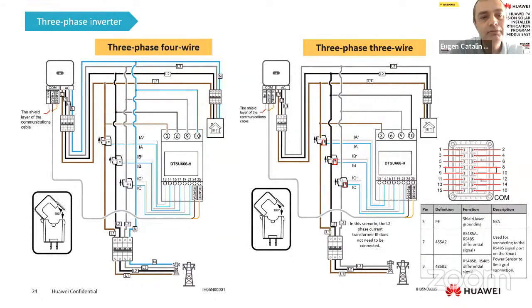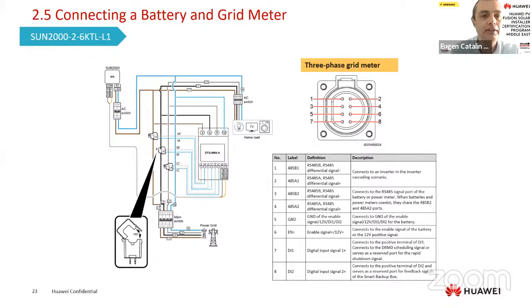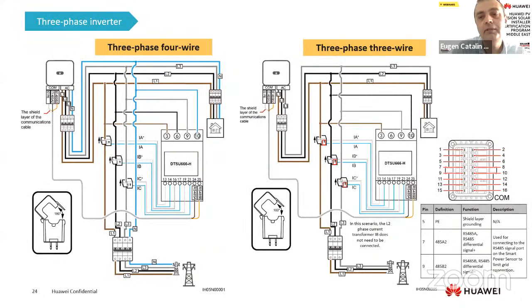In a three-phase inverter, we'll have a three-phase meter only. Here in the L1, we can also have a single phase, of course. Here is an example with a three-phase. Single phase will be in a single-phase system, and the connection is the same in 3 and 4. Here we have the M1 three-phase inverter with 2 connection ways. One is with neutral, and the second one is without neutral. I think this is very rare. In any situation, the meter communicates with RS485, of course, and the position on the communication port of the inverter will be 7 and 9.